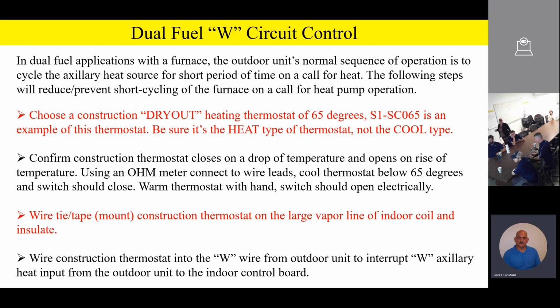Then take that little construction thermostat and hold it in your hand for a couple of minutes, and click. You'll see that it'll open above 65 degrees. So the point is, if you're unsure what the thermostat activity is, go ahead and double check that and confirm it with your ohm meter and a glass of ice and your warm hand. You can operate that switch. The next thing you're going to do, you're going to wire tie or tape, you're going to mount this construction thermostat on the large vapor line of the indoor coil, and you're going to insulate it.